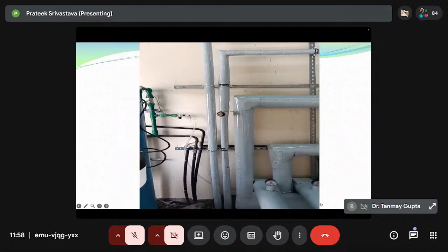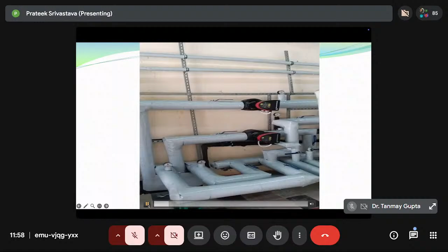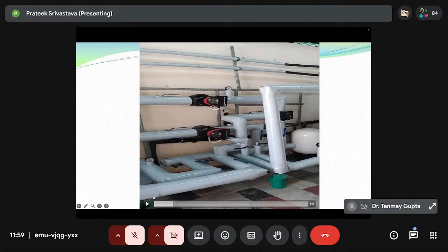Okay, so we have a small video of this plant. If you see, we have two pumps here. They are supplying chilled water to radiant and fan coil units. We have a mix-it unit here. In this unit, chilled water comes at 8 degrees Celsius and the unit divides it into two. One 7 or 8 degree stream goes to the fan coil unit, and the other it mixes with the return water temperature, creating 16 to 17 degrees Celsius and sending it to the radiant cooling system.